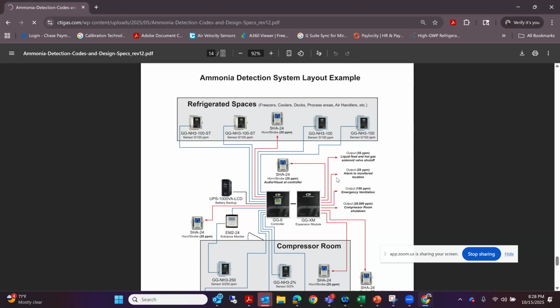Well, to update some of the other systems, you'd have to come back in, of course, and pull wire, expand the expansion modules, and pull wire all the way back out to those new buildings and new areas to get them covered. And you'd have to pull more wire and maybe even more power supplies for powering your lighting. That's your additional lighting that you're going to need out there too, right? So that's quite a bit of labor to pull all that clear through the entire new add-on.